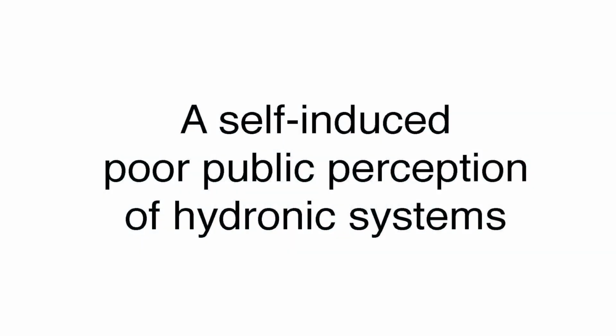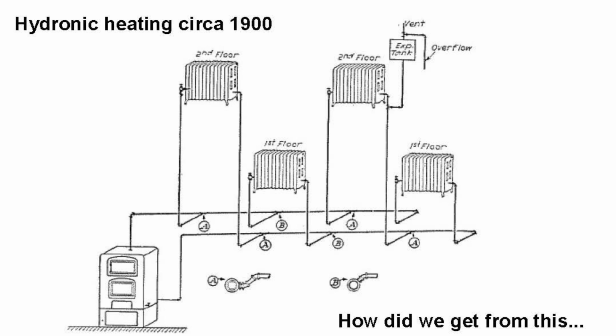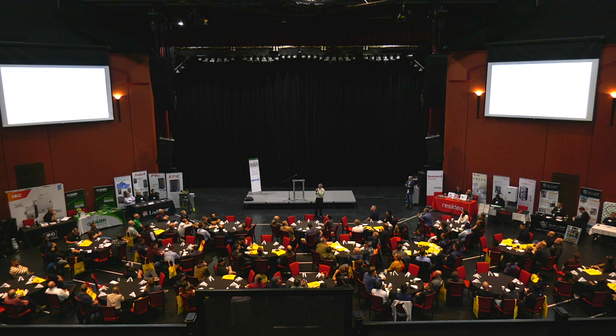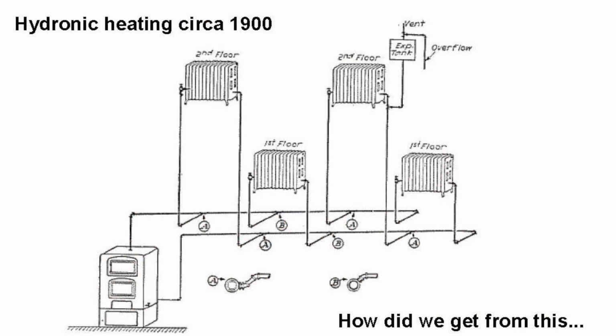How about this? A self-induced poor public perception of hydronic systems. This is what a hydronic system was in the 1900s. I'm amazed at what the engineers created back then. You know, you look at it and say, well, that's old, that's antiquated. Well, they did things like they sloped the piping. They had very specific fittings, if you look down at the bottom there, that were designed so that just the buoyancy difference between hot water in the boiler and cooler water after it has flowed through the radiator, that's all that created the circulation in that system. And, you know, we call those gravity systems or thermosiphon systems, and they worked, okay? And you didn't need an app to run them.